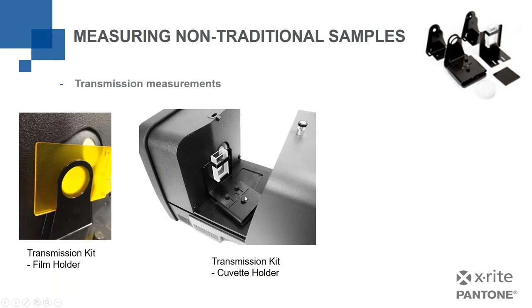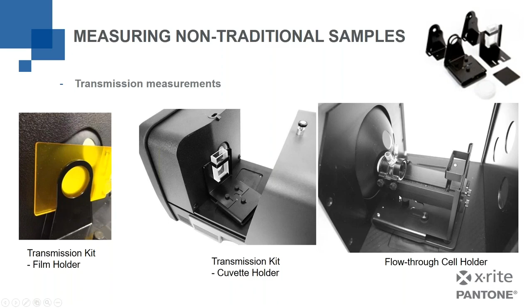And so now you can see this transmission kit. It's very nice because it's magnetically connected into a few pins. And so you literally set it in place, it locks in place. Now I've got a cuvette in place to be able to have measurements of some liquids. And we even have something called a flow-through cell holder. So this is like a cuvette, but you can see there's 2 arms coming off of that where hoses could be connected, and I could literally be passing a fluid through that cell and testing it, measuring it, pump more fluid through and test again. So it's for continuous kind of monitoring or measurements, series of measurements on liquids.